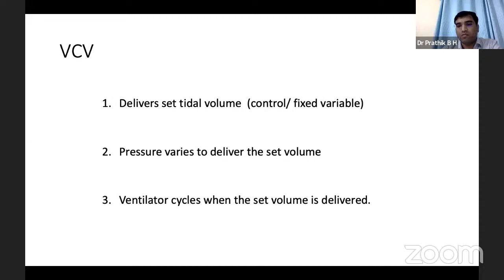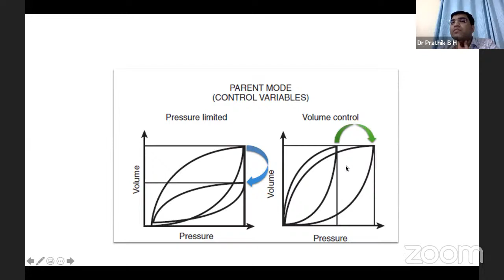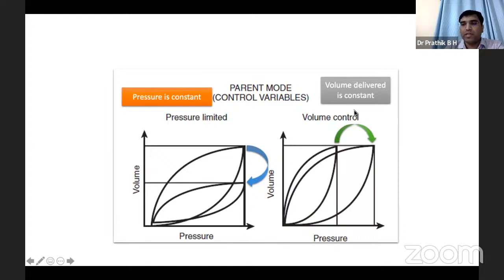Let us see the difference between the commonly used pressure limited or pressure controlled ventilation and volume controlled ventilation. In pressure controlled ventilation, it is the pressure which is prefixed. That is, pressure is fixed, and the volume delivered into the patient's lung depends on the compliance of the lung. If the compliance of the lung is very poor, then the tidal volume delivered will be less. If the compliance is good, the tidal volume delivered will be more. In volume controlled ventilation, as I told, the control variable is volume. That is, the pressure changes to deliver this tidal volume. You can see here, if the lung is too stiff, that is, if the compliance is less, then more pressure is required to deliver the same fixed tidal volume. So in pressure limited, pressure is constant. In volume limited or volume controlled modes, the tidal volume delivered is constant.